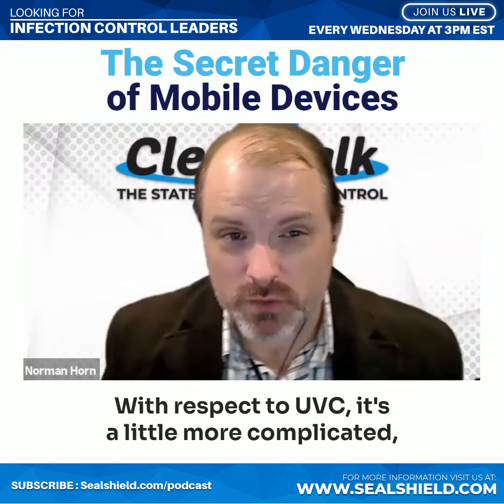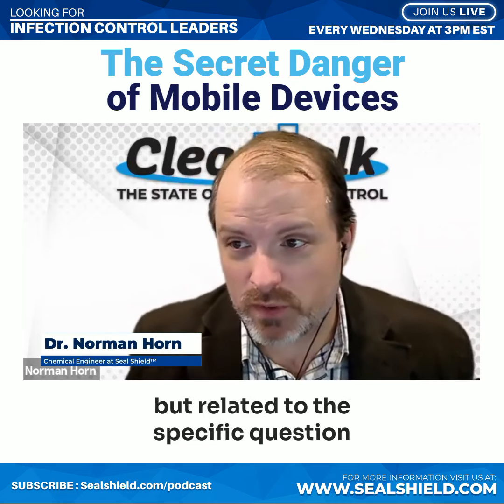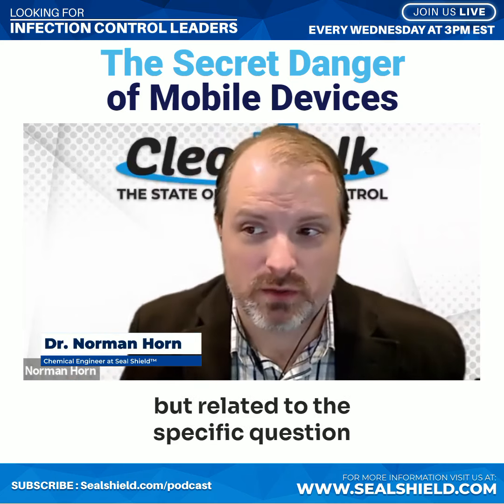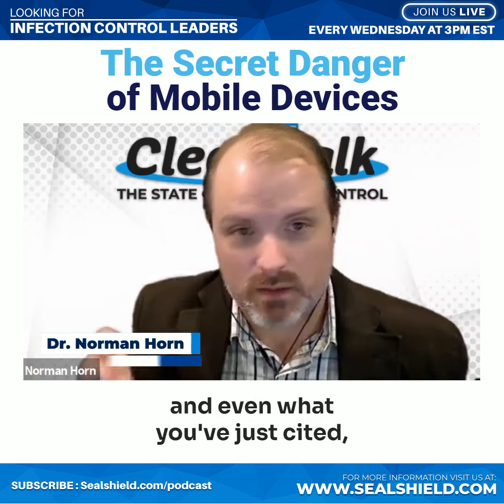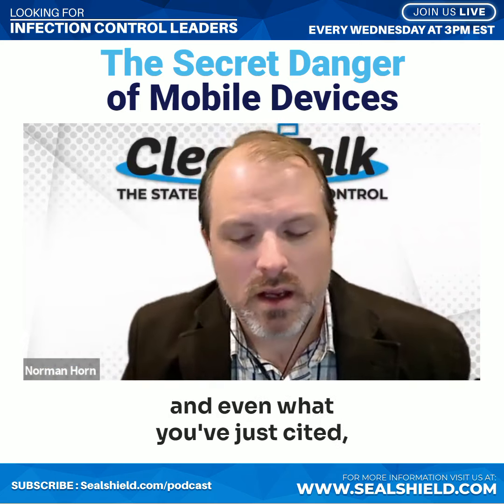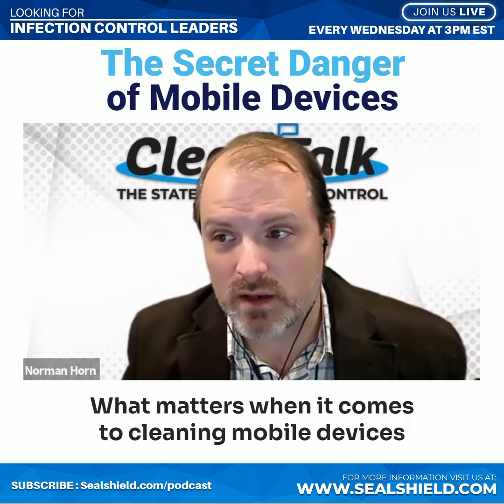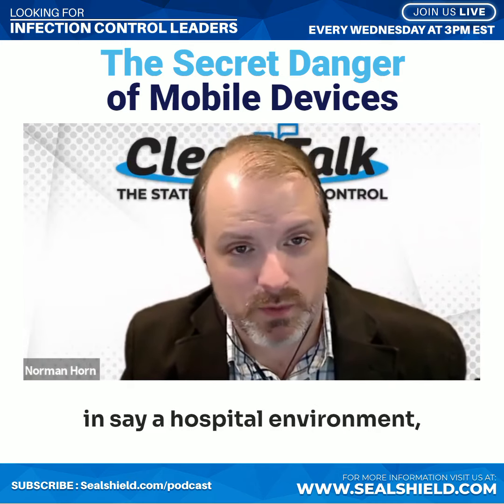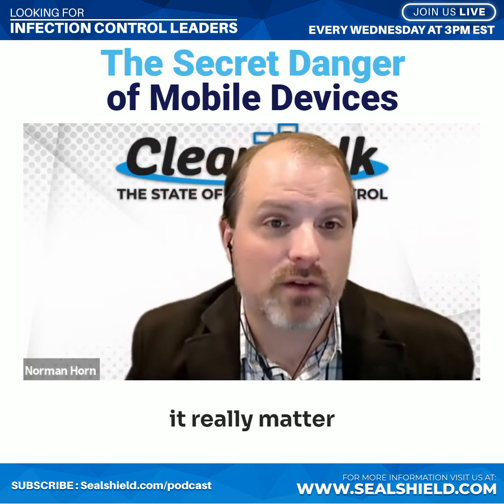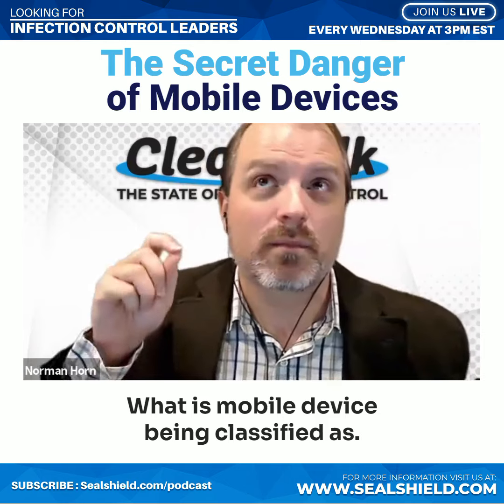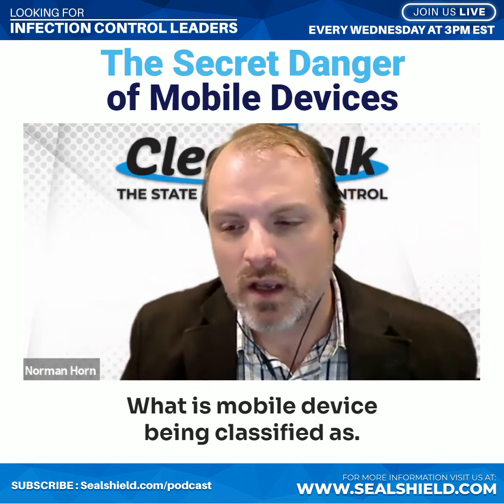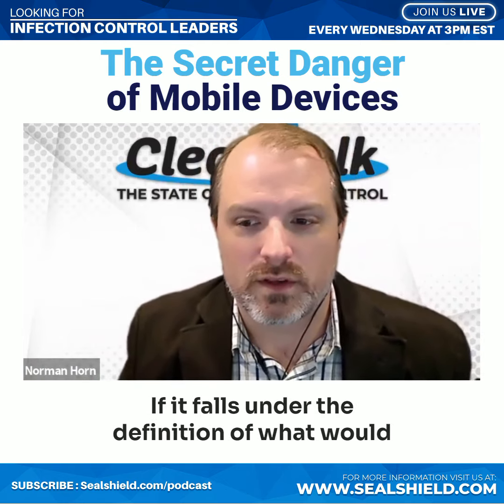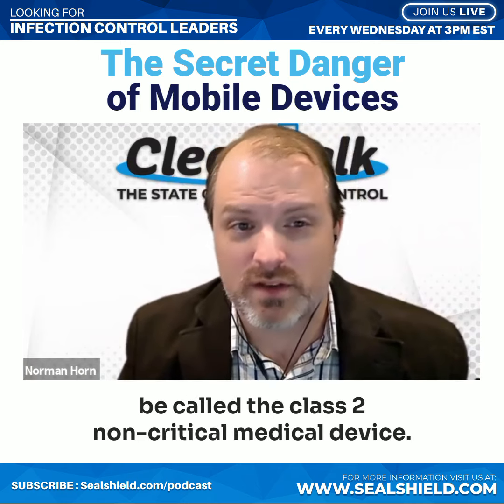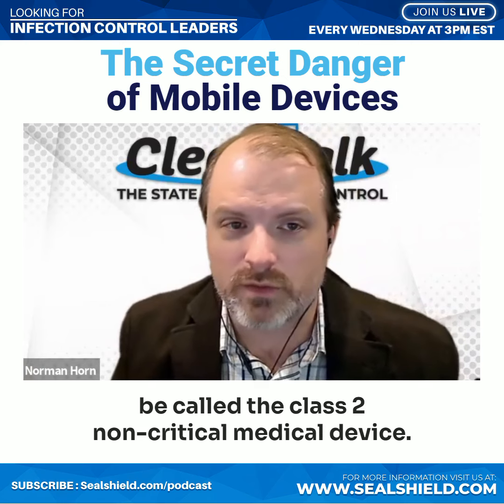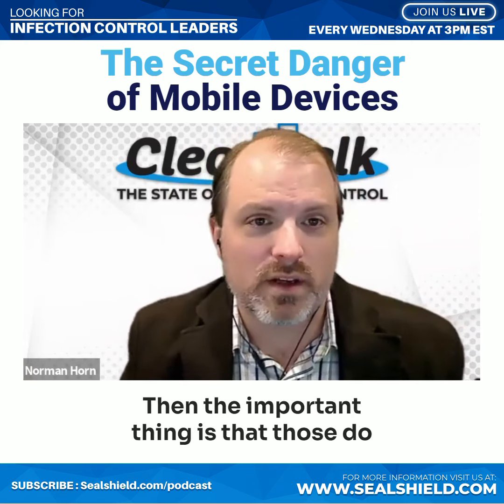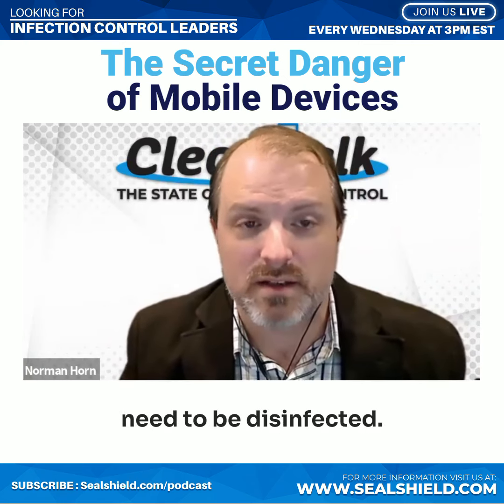Okay, with respect to UVC, it's a little more complicated, but related to the specific question regarding mobile devices and even what you've just cited, what matters when it comes to cleaning mobile devices in, say, a hospital environment, it really matters. What matters then is what is the mobile device being classified as? If it falls under the definition of what would be called a class 2 non-critical medical device, then the important thing is that those do need to be disinfected.